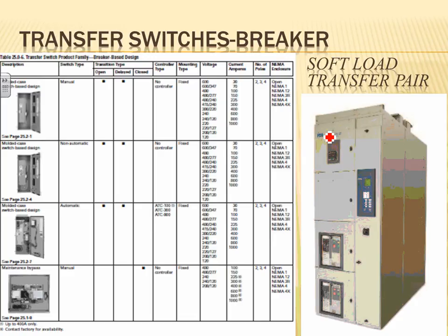Any questions? All this information is from Cutler Hammer, especially the one on this side here. These are the pictures I got from here. I can't remember if it's Cutler Hammer or ASCO. Any comments about the transfer switch technologies? Smaller auto transfer switches tend to be contactors. Bigger auto transfer switches tend to be circuit breaker technology.